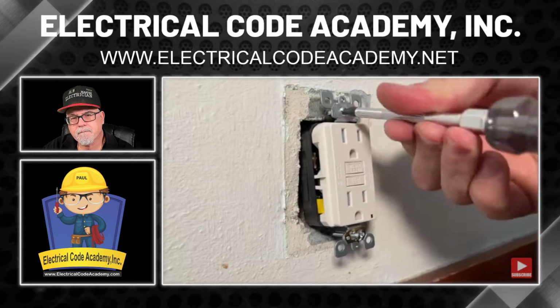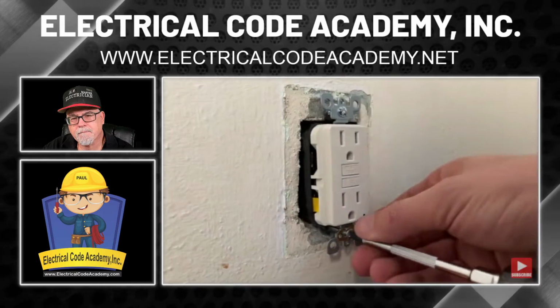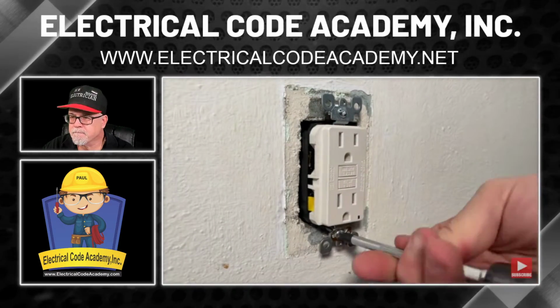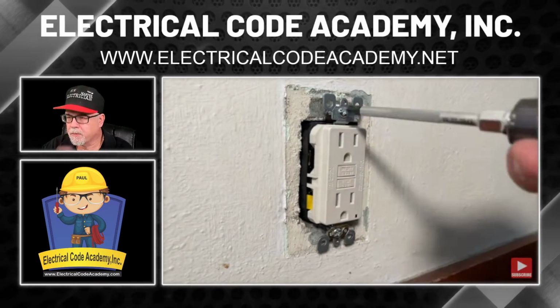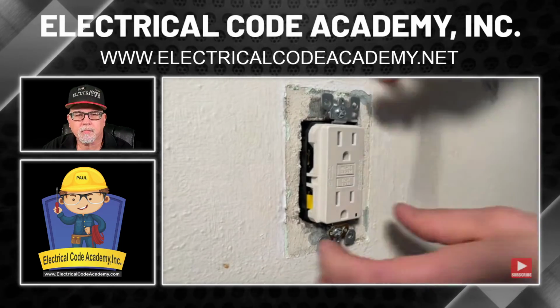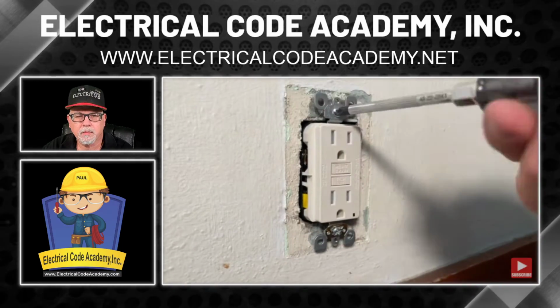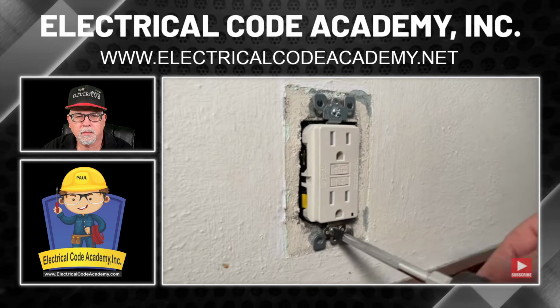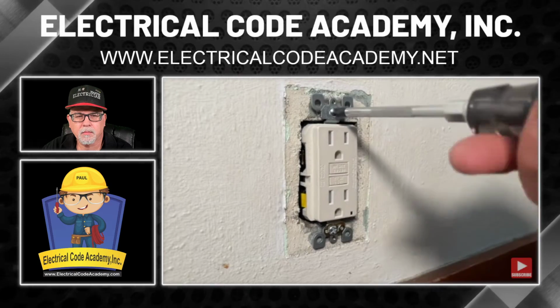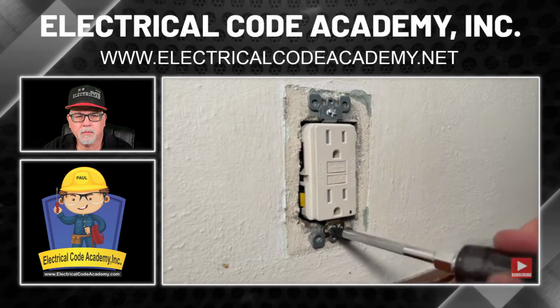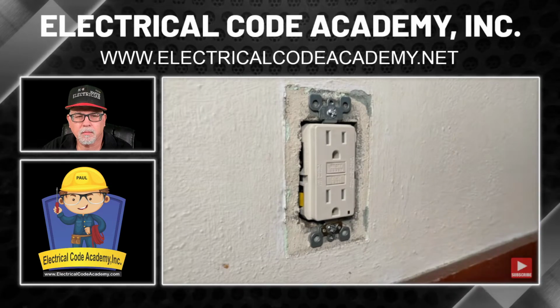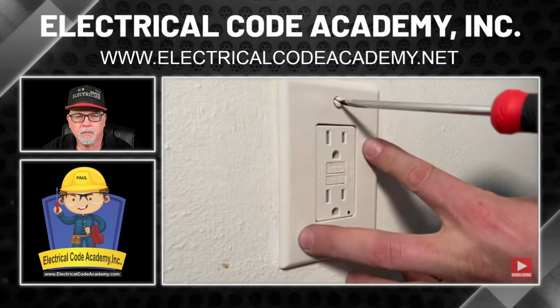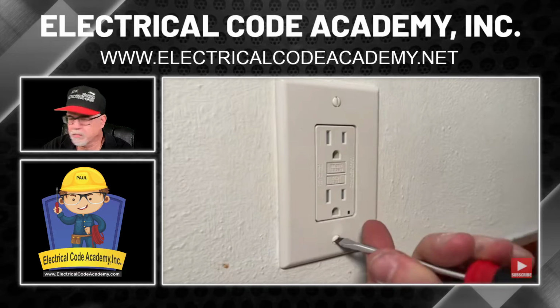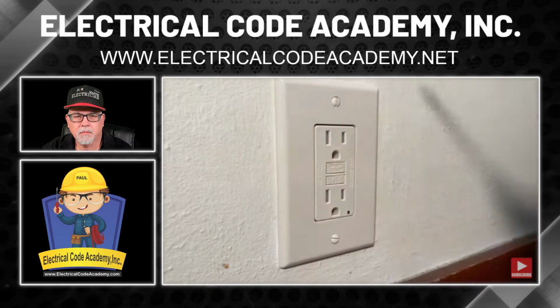Just a couple more screws and we'll be done. So we'll reinstall the mounting screws. I work back and forth and also make sure that the receptacle is centered so you don't get it tightened down and kind of cockeyed in the box. Now once you have that tightened down, we'll do a standard Decora faceplate and then tighten down both of the screws. Then we'll test it out.